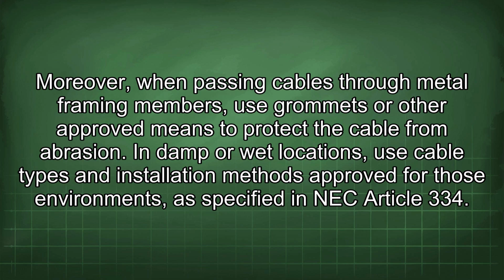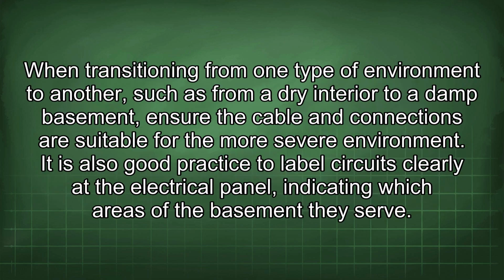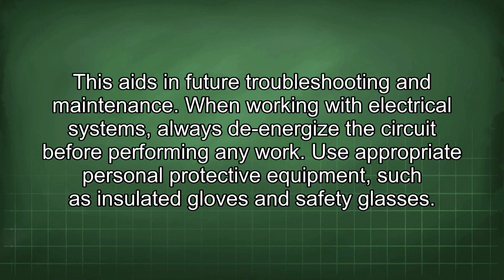Moreover, when passing cables through metal framing members, use grommets or other approved means to protect the cable from abrasion. In damp or wet locations, use cable types and installation methods approved for those environments, as specified in NEC Article 334. When transitioning from one type of environment to another, such as from a dry interior to a damp basement, ensure the cable and connections are suitable for the more severe environment. It is also good practice to label circuits clearly at the electrical panel, indicating which areas of the basement they serve. This aids in future troubleshooting and maintenance.